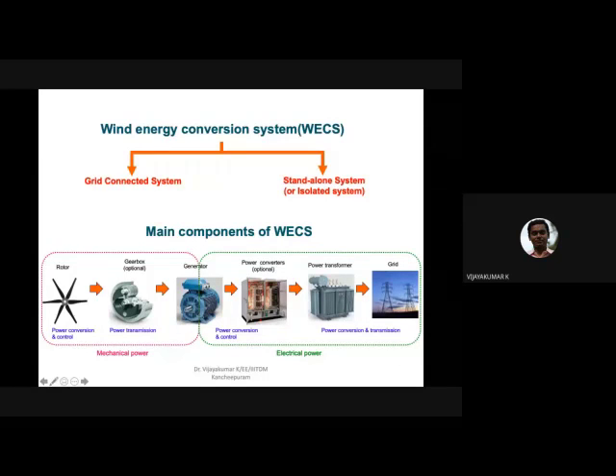Power transformer, one purpose is to match up the voltage of the wind turbine and the grid, right? So if it's 11 kV here and your grid is 33 kV, then you have to use the power transformer to match the voltage. That is one purpose. Another important purpose of the transformer is isolation. It will give electrical isolation between the grid and the system. So if any fault occurs here, it won't be transmitted much into the grid. If any fault happens there, it won't affect your wind turbines. So that will provide the electrical isolation of the system.